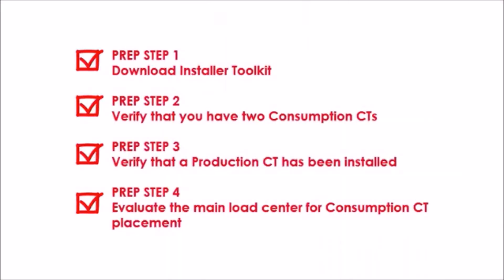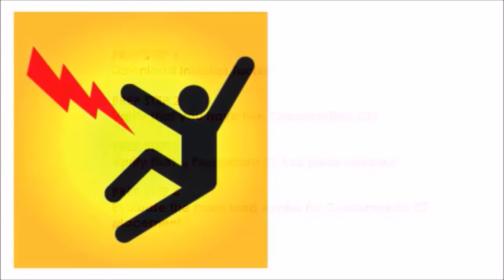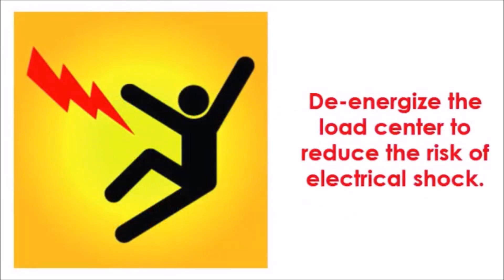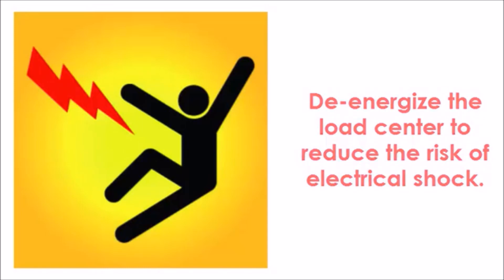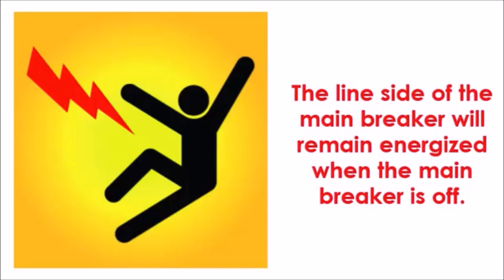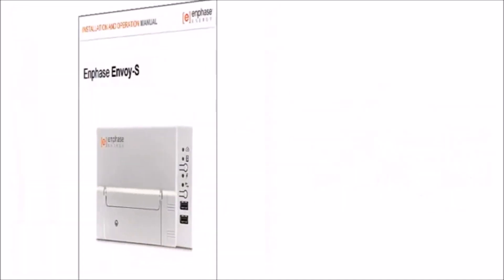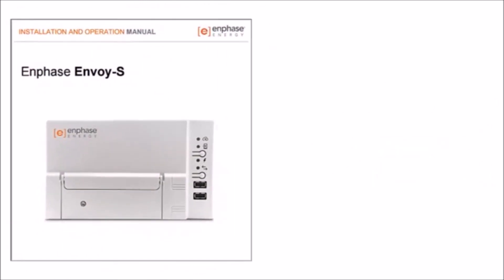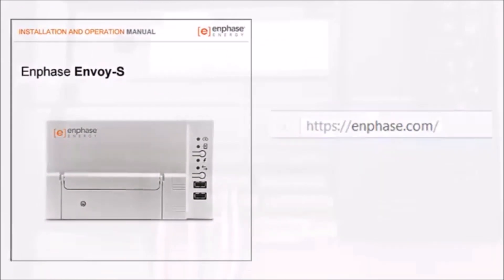You have now completed preparations and are ready to begin the consumption CT installation process. Before installing CTs, always de-energize the load center to reduce the risk of electrical shock. Be cautious. The line side of the main breaker will remain energized when the main breaker is off. For additional safety information, please reference the Envoy-S Installation and Operation Manual on Enphase.com.